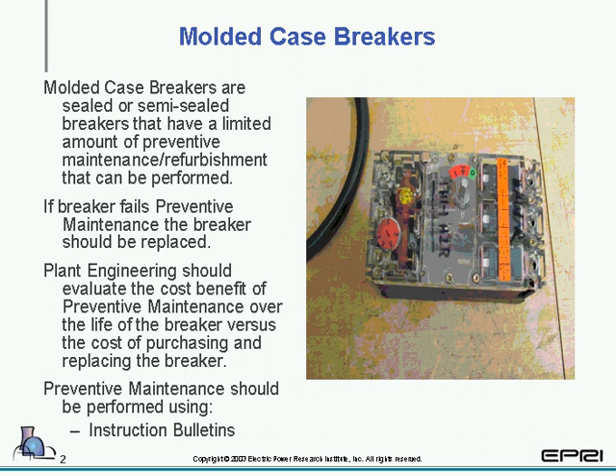So how this is broken up is right now we're going to talk about preventative maintenance from beginning to end. Then we will take a look at overhaul and where and when it fits into your PM program. Very first item up on your screen is your molded case breakers. Most of them, as we talked about in session 1, are sealed or semi-sealed and have a limited amount of preventive maintenance or refurbishment that can be performed. And each plant needs to decide at what level it is cost effective to do maintenance on them versus replacement or upgrading to a newer design or model.